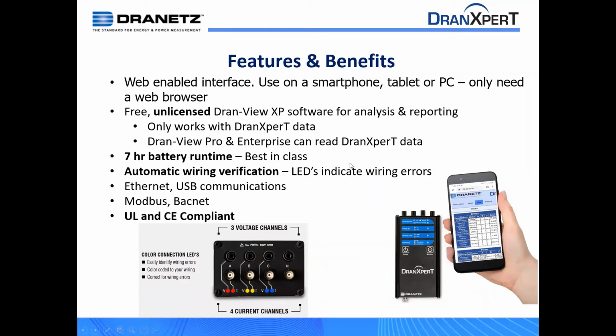So again, another huge benefit, best in class in the industry, is a 7-hour battery runtime. And that's a lithium-ion battery, so it has a very large capacity to it. Automatic wiring verification, and you can see that down here when you configure the meter for a particular wiring configuration, it detects whether that's correct. So as an example, if you set it for a delta configuration and you wire it as a Y, these LEDs are going to start blinking at you to basically say, hey, something's wrong.